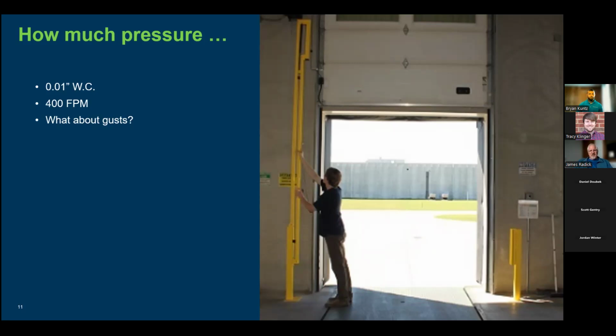I've been in so many buildings that have a negative pressure in them. A cold gust comes in and it'll shoot 100 or more feet into the building, making everybody in that area very uncomfortable. If you've ever been in buildings in the wintertime and saw ice by the dock doors coming in on the floor, that's because the building was negative and that cold air is just coming in and keeps rushing under the door.